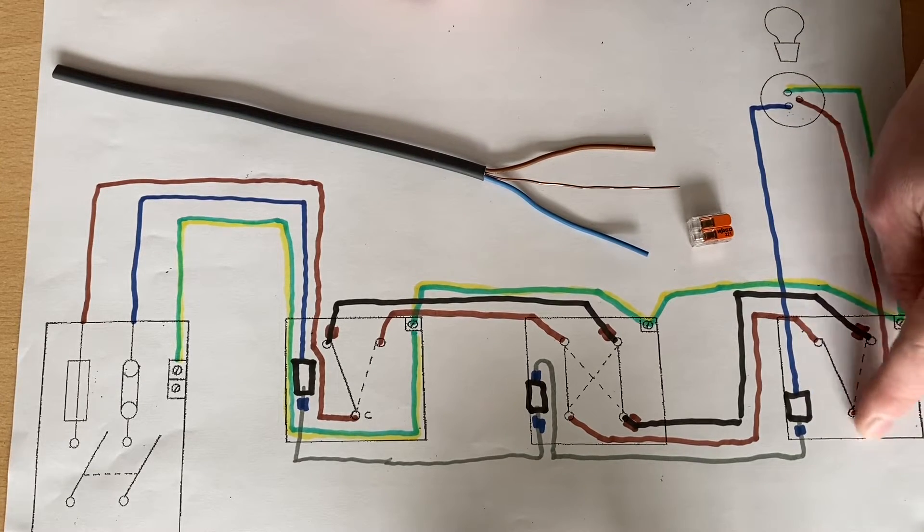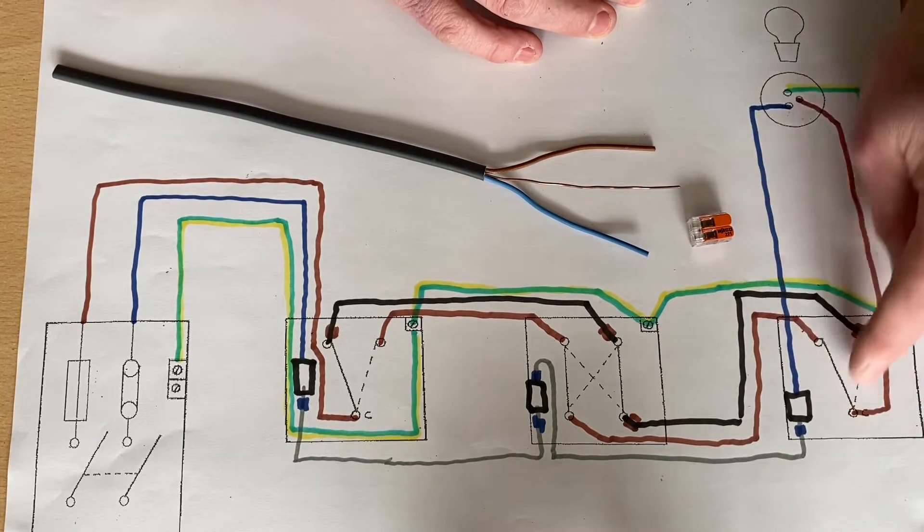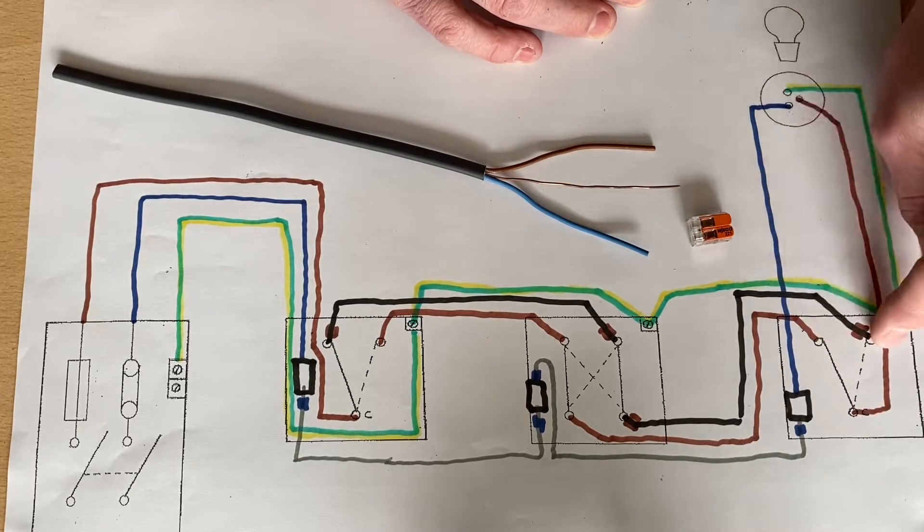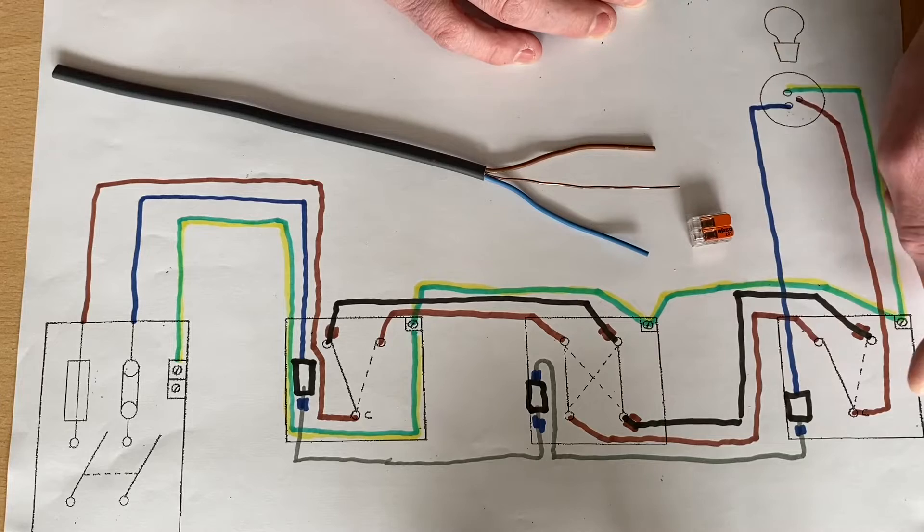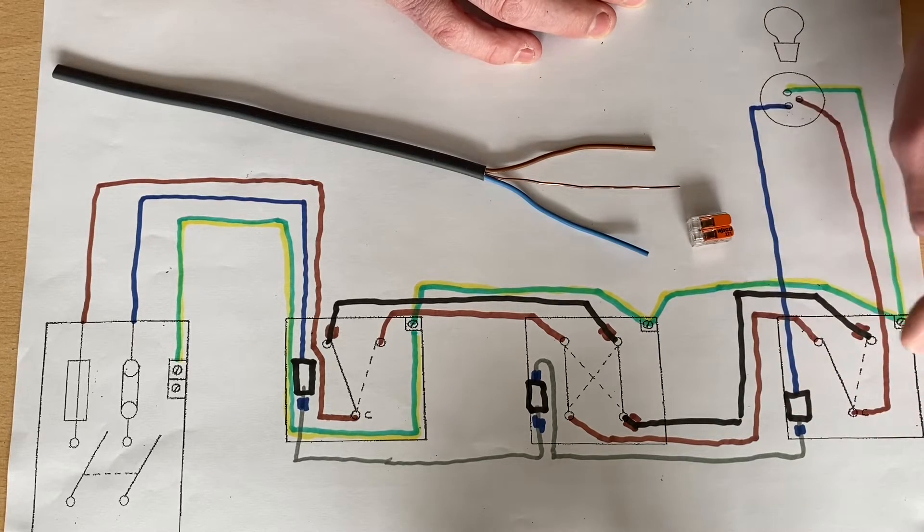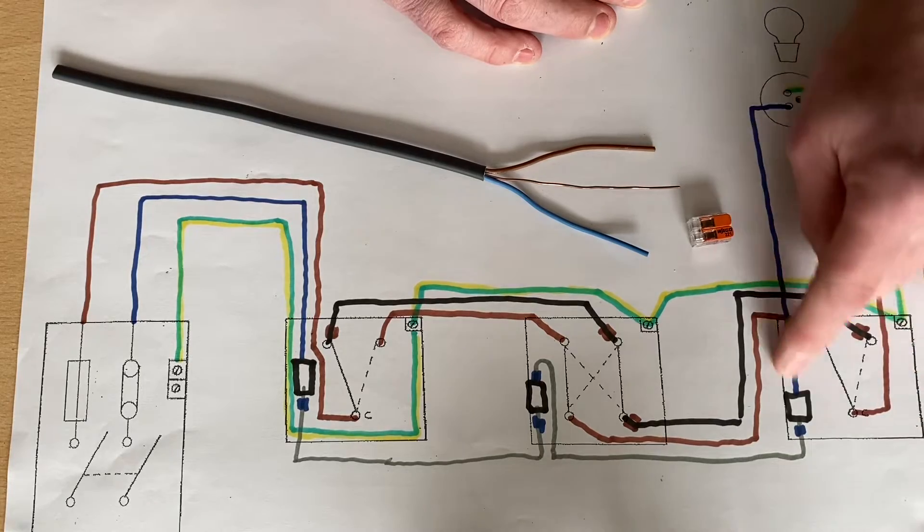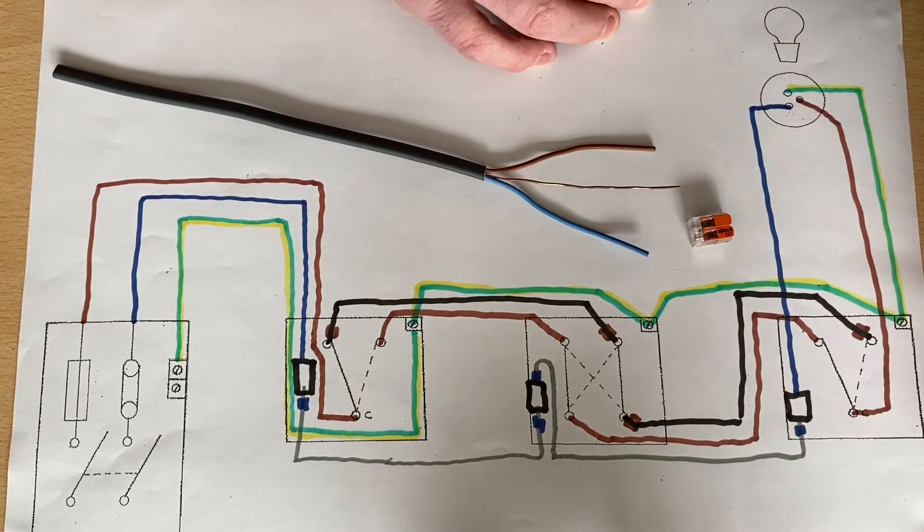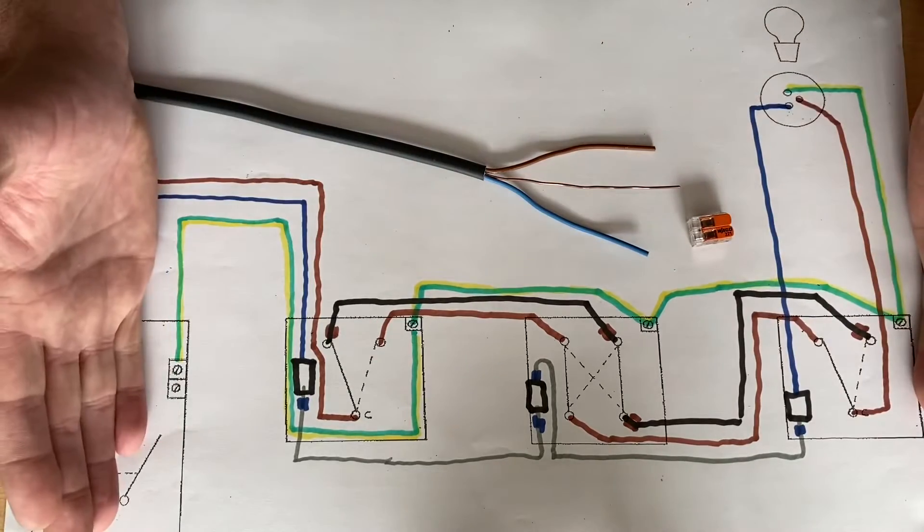Well, this one here will be only energised when the lighting point is on, and we can't guarantee that these will remain on at all times as we flick between our switching sequences. So therefore, you wouldn't be able to come out of this two-way light switch with a neutral, a CPC, and a permanent line connection to another room.